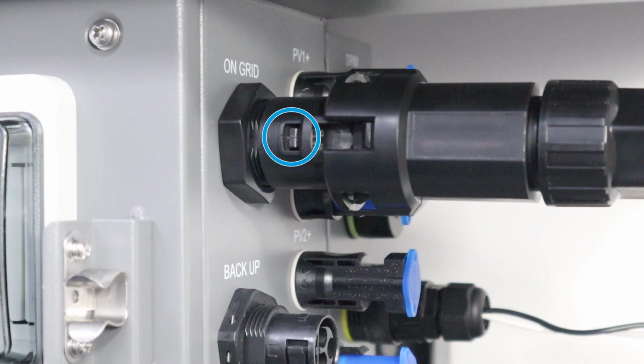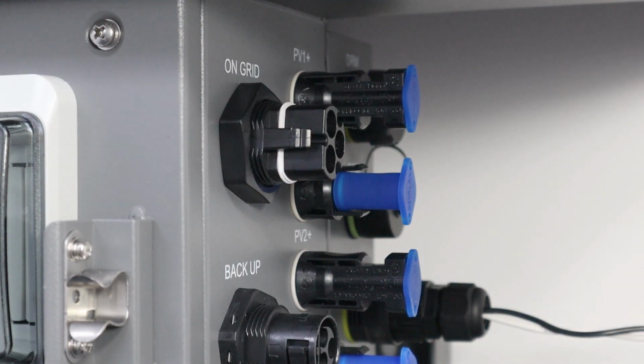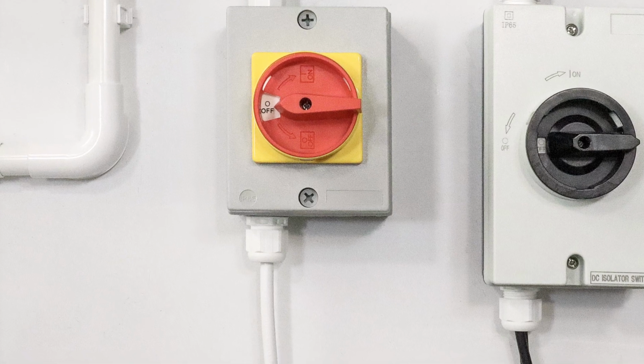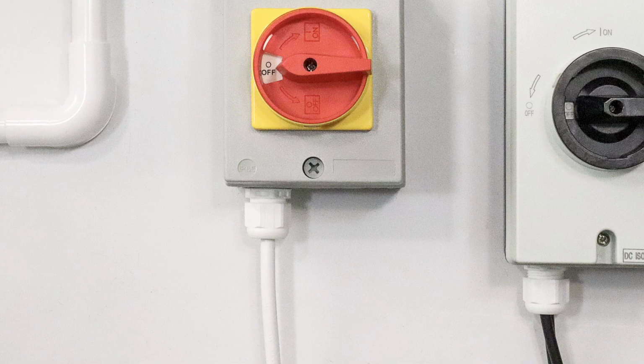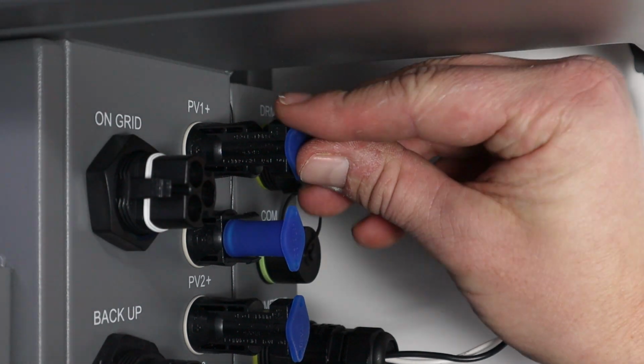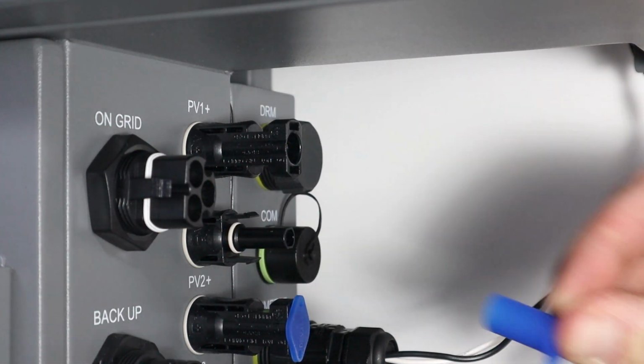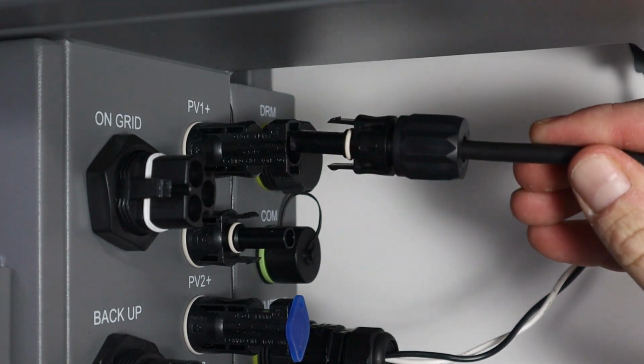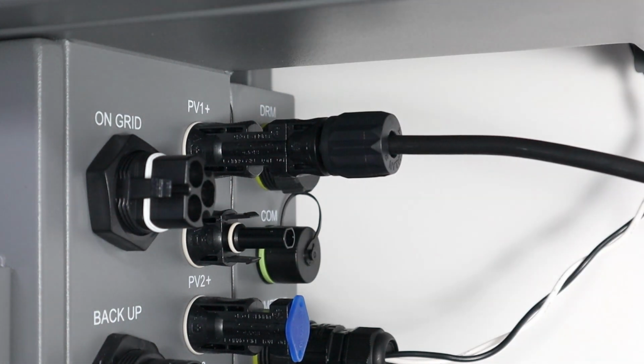Note that in the event that you might need to remove this plug, this can be done by depressing the retaining clip with a flat screwdriver blade and sliding the plug off. Connect the other end of the AC connection to your inverter isolator switch. To connect the PV side of the inverter, remove the rubber stoppers from the positive and negative PV1 sockets.